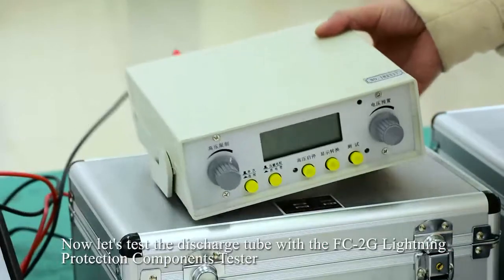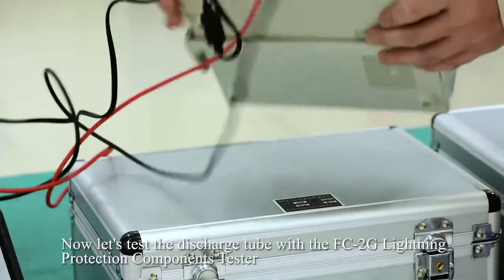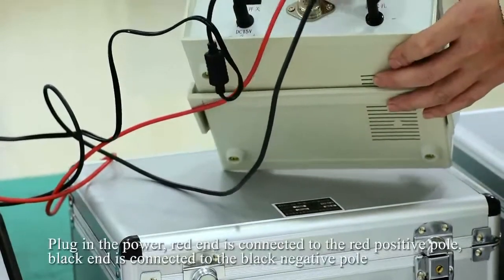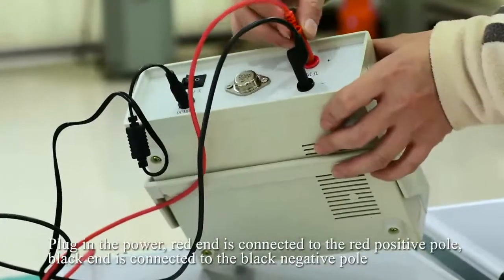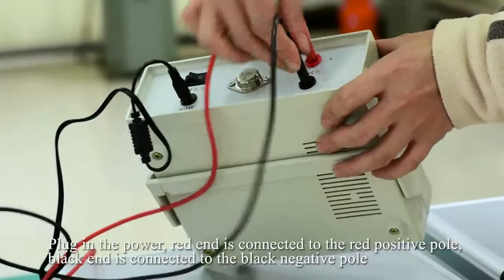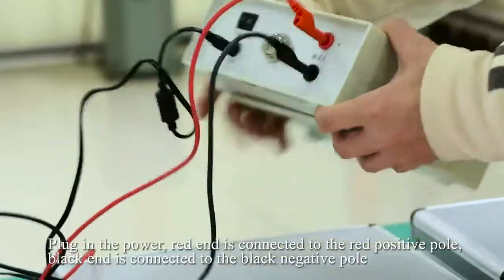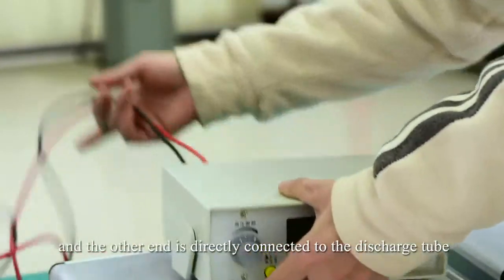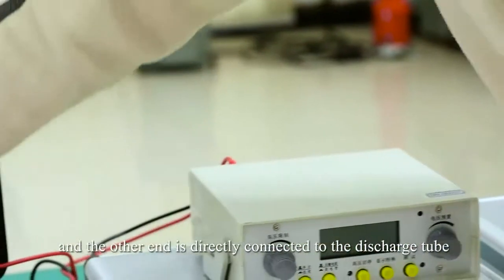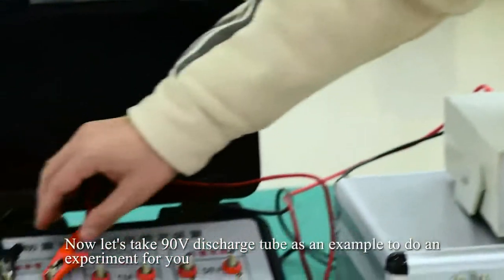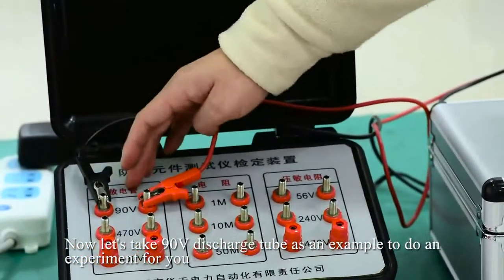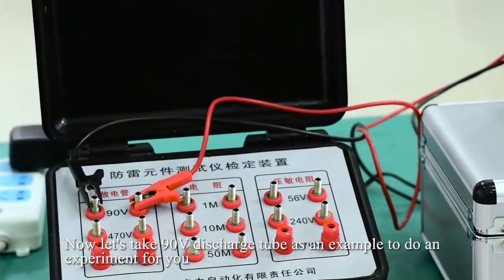Now let's test the discharge tube with the FC-2G lightning protection components tester. Plug in the power, red end is connected to the red positive pole. The black end is connected to the black negative pole, and the other end is directly connected to the discharge tube. Now let's take the 90V discharge tube as an example to do an experiment for you.